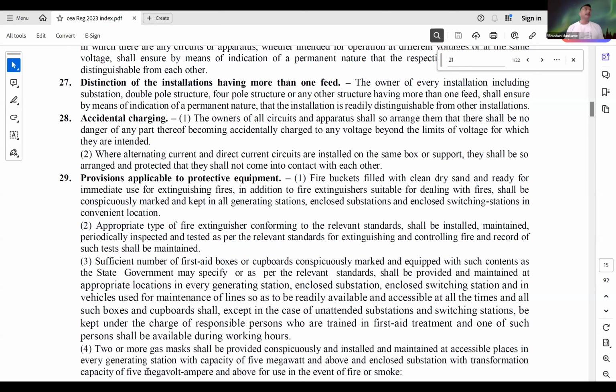This is missed out. Second, if a particular type of fire is taking place, we must use a particular fire extinguisher. So the do's and don'ts in case of fire differ. The technical staff, the maintenance staff, and the firefighting team should sit together and discuss the plan for when this kind of electrical accident or fire takes place at our location. What should be the steps? What should we do and what should we not do? Which fire extinguishers to use? Which should not be used? This has been particularly mentioned in Regulation 29, that you have to follow the particular standard as per the type of fire.